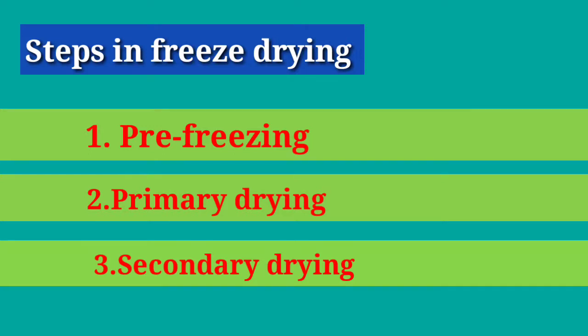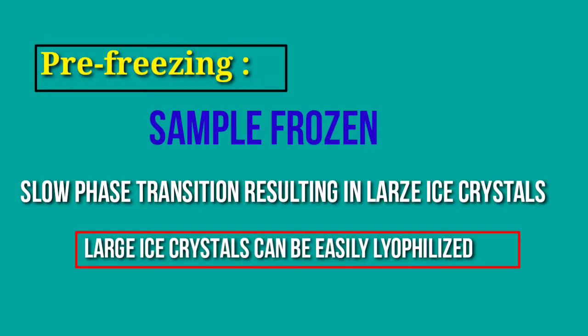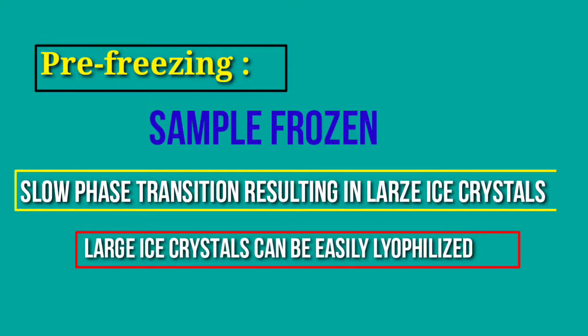Let us start with pre-freezing, which is an important step. During this process the sample gets frozen — this is a slow phase transition, resulting in large ice crystals. The liquid to solid transition is made to take place slowly in a controlled manner, so that large ice crystals can be formed which can be easily lyophilized during the process.